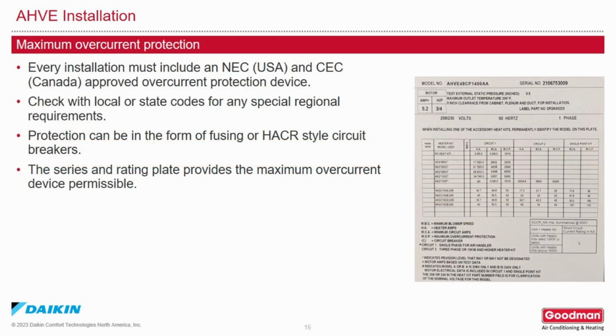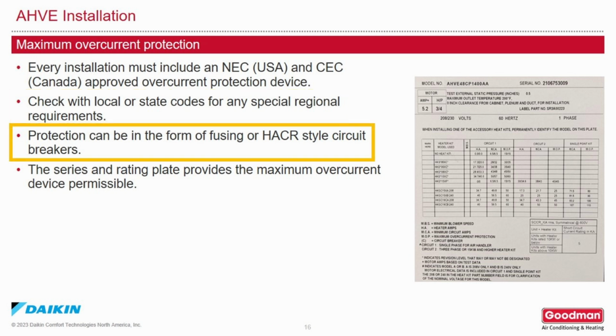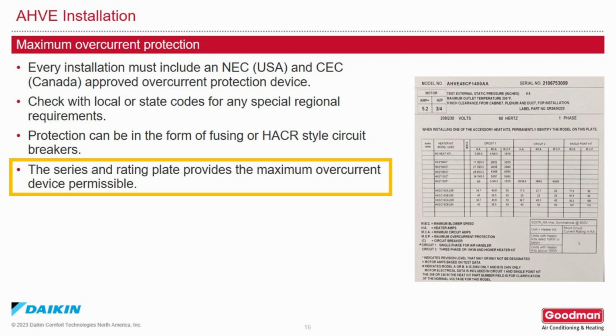Maximum overcurrent protection. Every installation must include an overcurrent protection device that is NEC in America and CEC in Canada approved. Check the local and state codes for any special regional requirements. Protection can be used in the form of a fuse or HACR-style circuit breakers. The data tag on the unit will provide the maximum overcurrent protection device that is permissible.